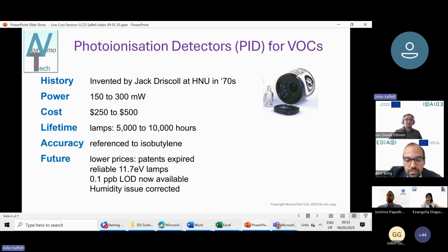Prices are going to come down because some critical patents have expired. Most lamps are what's called 10.6 eV, but now 11.7 eV lamps, which let us measure a lot more things, are finally becoming reliable. And the humidity issue, which has always been a problem with these, has now been corrected.